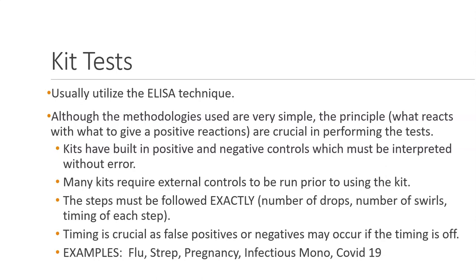The steps must be followed exactly. The correct number of drops, the correct number of swirls if that's involved in the procedure, and the timing of each step. In fact, the manufacturer will state that if results are read that exceed the time limit, the results are invalid. And again, I had an incredibly hard time convincing these folks that you can't just run off and leave it. You have to have a timer, and if it exceeds the timer because you're off doing something else, then you have to repeat the test.